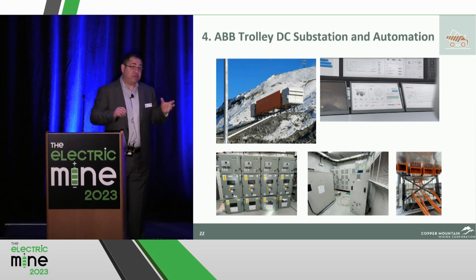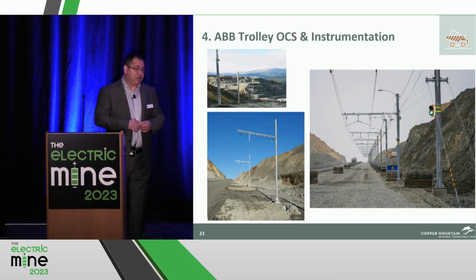There's also instrumentation mounted in the OCS to monitor things like the load height, when they're struck or not, and also light indications to tell the drivers it's okay to approach the line or not. So there's a red-green light traffic system in there. On the OCS, you can see some of the instrumentation. There's also current sensing that needs to be monitored to make sure we do not exceed the capacity of the line. So all of it comes together as an integrated system to work with the rest of the trolley assist to supply the trucks.